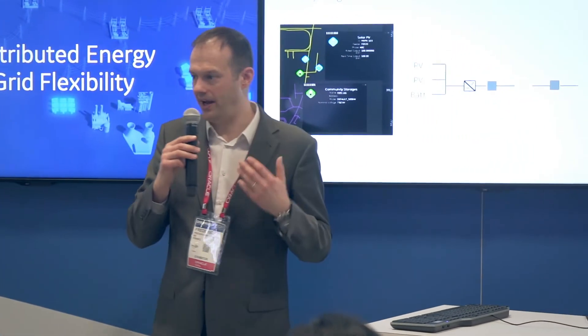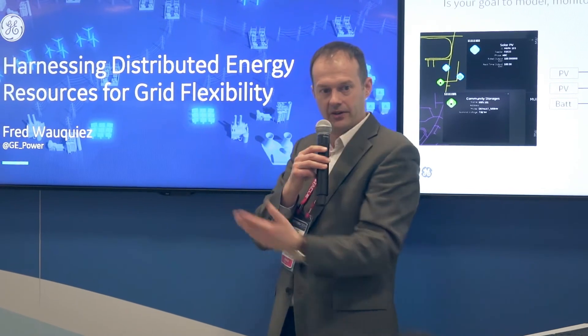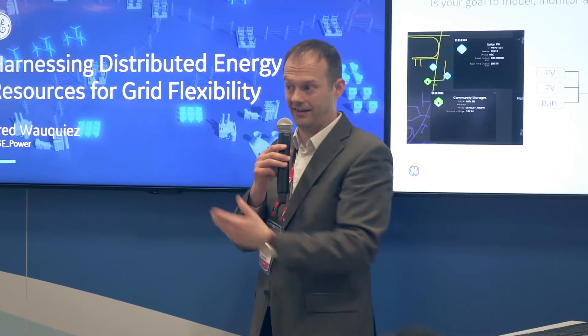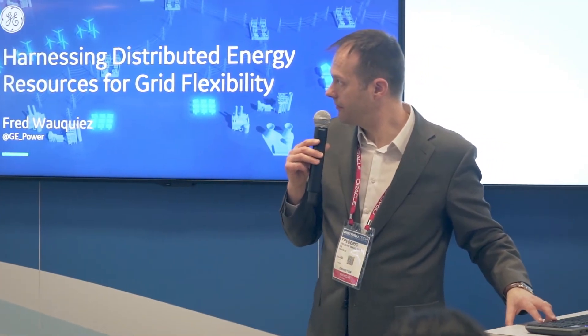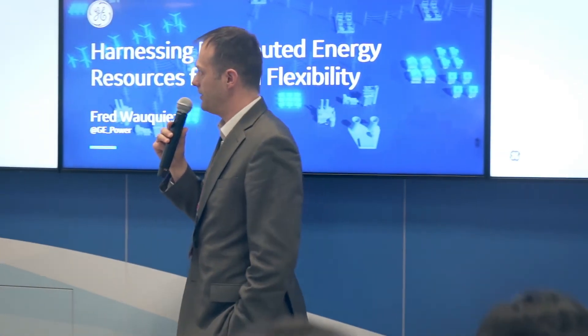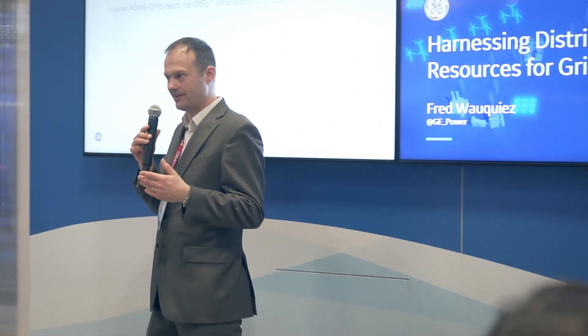So this is really a journey. You're not Bavaria or California yet maybe, but you need to start on this — it's a lot of work. The next question is: I've modeled these assets, but my daily job is fault location, isolation, and service restoration. How does that work when there are PVs around? When I want to re-energize a feeder and send crews to the field, am I sure there is not a PV still energizing that feeder? Within the process of restoring a fault, is there a step checking these things linked to DERs?